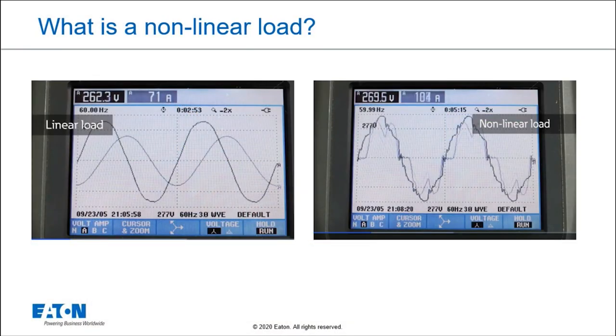Let's take a look at this picture. Right here on the left we have what we would call a linear load. The voltage, the higher waveform in this case, is a nice clean 60 Hz sine wave. The current is also a nice clean 60 Hz sine wave, meaning the current looks like the voltage. And in fact, when the current looks like the voltage, we call that a linear load.